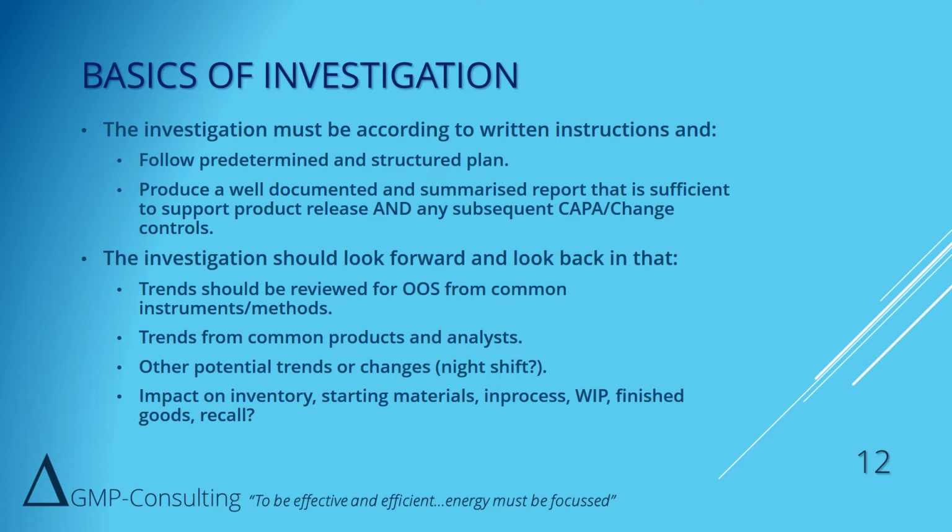The investigation should always look forward and look back, in that if it's analyst specific or instrument specific, it may be more than one batch that's involved. Look for trends in common products and analysts, other trends like changes of shifts and things like that, and what is the impact on materials, inventory out in the marketplace, work in progress. Once you start digging into these things, the tentacles can go a long way.